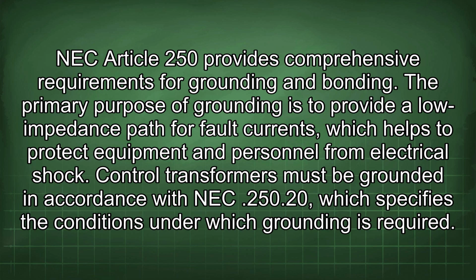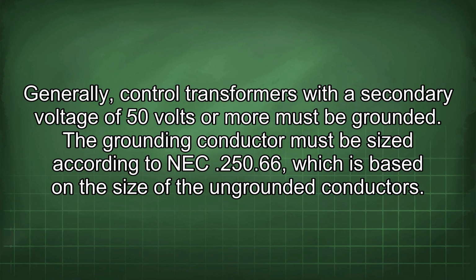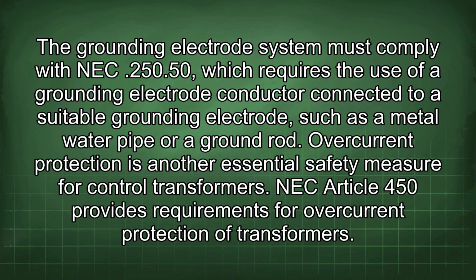Control transformers must be grounded in accordance with NEC 250.20, which specifies the conditions under which grounding is required. Generally, control transformers with a secondary voltage of 50 volts or more must be grounded. The grounding conductor must be sized according to NEC 250.66, which is based on the size of the ungrounded conductors. The grounding electrode system must comply with NEC 250.50, which requires the use of a grounding electrode conductor connected to a suitable grounding electrode, such as a metal water pipe or a ground rod.